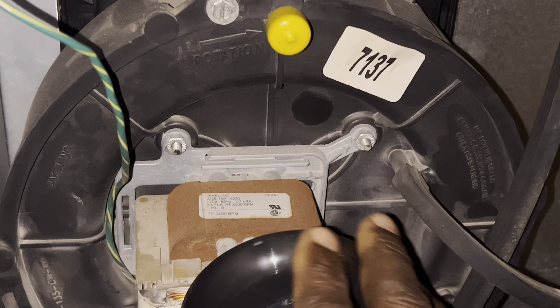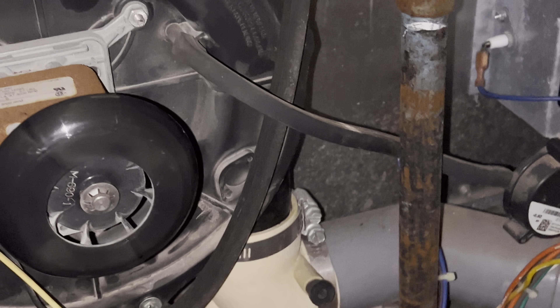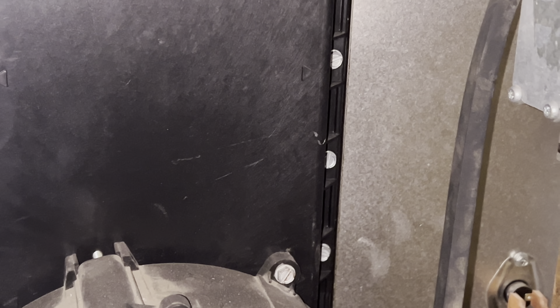Okay, so there's a couple of reasons why we'll have our flame rollout. If we get a weak combustion motor, or induction motor, or if we get a blocked flue exhaust. The main problem with a flame rollout is going to be a crack, or a hole in your heat exchanger.